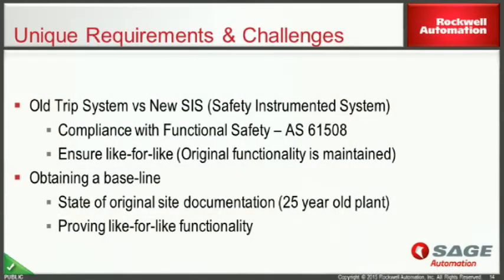Old trip system versus new safety instrumented system. We had to maintain compliance with 61508. The functionality of the new trip system had to be in line with the SRS and the HAZOPs and SRS that was developed, but we also had to ensure like-for-like functionality of the original trip system. You know, it's a hazardous process, so the customer really needed to be comfortable that we didn't miss any interlocks out, any safety critical interlocks that may not have appeared as part of the safety requirements of the new system.